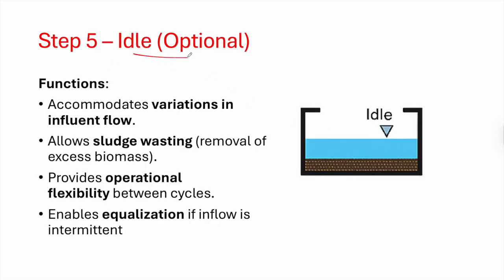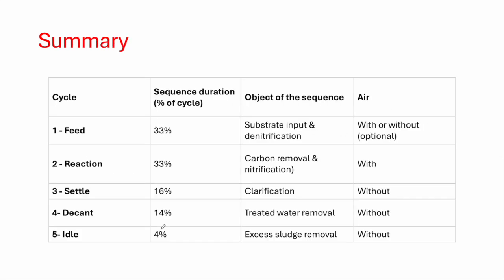The idle stage is optional and primarily used in medium-scale projects. It accommodates variations in influent flow, allows sludge wasting to remove excess biomass, provides operational flexibility between cycles, and enables equalization when inflow is intermittent.